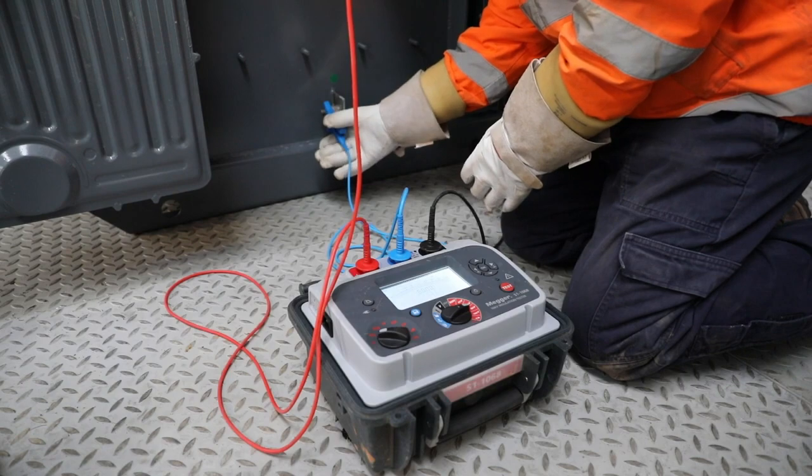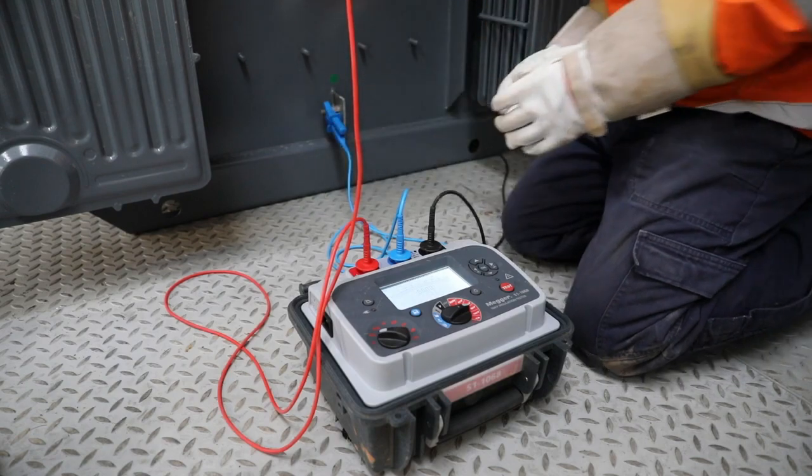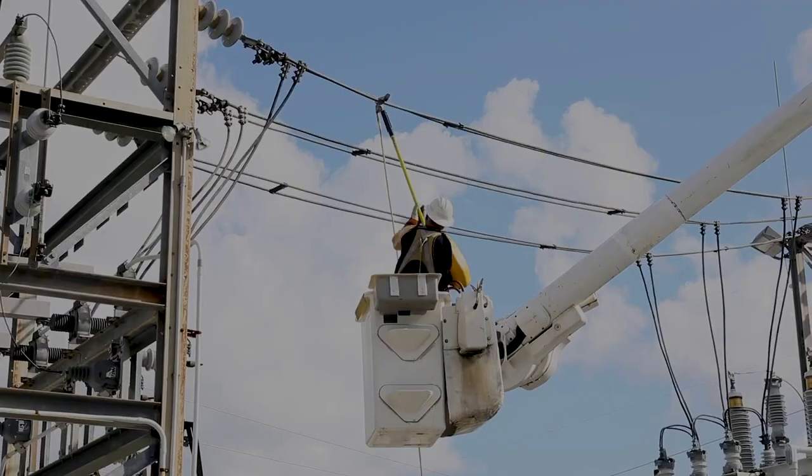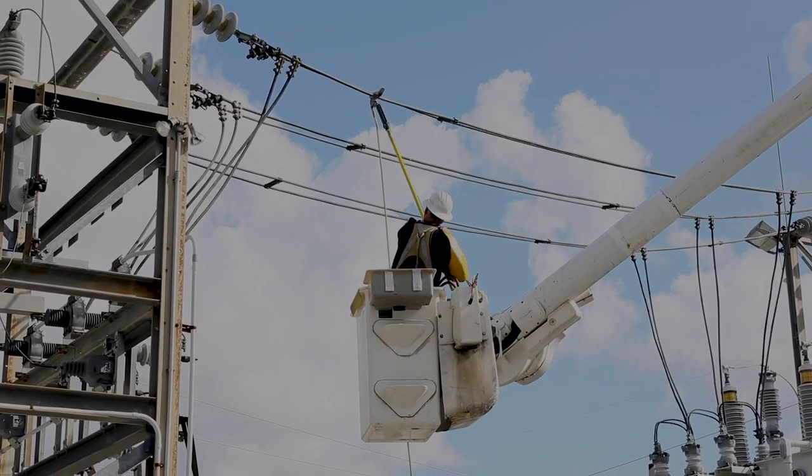These valid results from Megger's guard terminal can save you from costly replacements, ensuring you won't needlessly discard a potentially viable asset that may only need a clean.